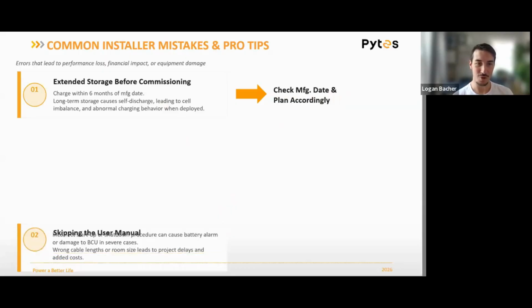So some pro tips for installing these high voltage systems - they are different enough from the low voltage resi side batteries that there's a few things you want to be aware of. My biggest one is extended storage before commissioning. Given that the batteries are in series, they have a much more difficult time balancing compared to a parallel install. So you want to make sure you're planning your ordering and installation accordingly. Check the manufacturing date on the batteries and make sure we are recharging those batteries every 6 months. If not, that can lead to annoying balancing issues when you go to do your install.